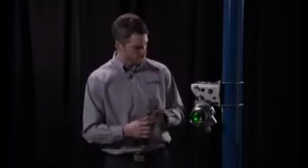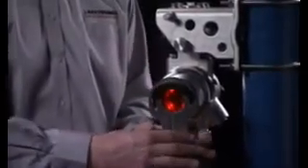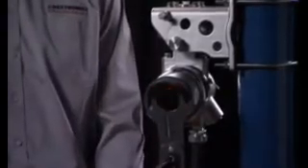I know that this device is set up so that 2 of those test films will help me achieve a low alarm. So if I put those 2 films on there, I should be getting a flashing red LED. That's good. That means I've achieved my low alarm.